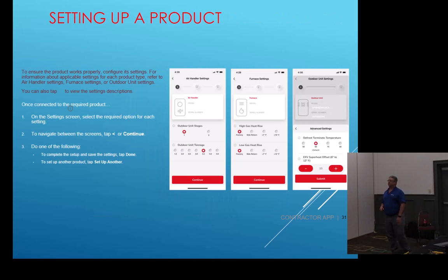If you're setting it up with a 24-volt system, you're using the contractor app, it may ask you some different questions in here, whether it's a single stage or two stage. Okay? What tonnage it is. If it's a furnace, it comes from the factory setting for the return coming in the bottom. I don't know if anybody does any side returns, but if you do any side returns, you need to select side return here because the torque value of that air pulling across that motor is different, and you have different temperature rise going across that heat exchanger. Okay? So it needs to know about that. You may not get the airflow that you want out of it if you leave it at factory setting.